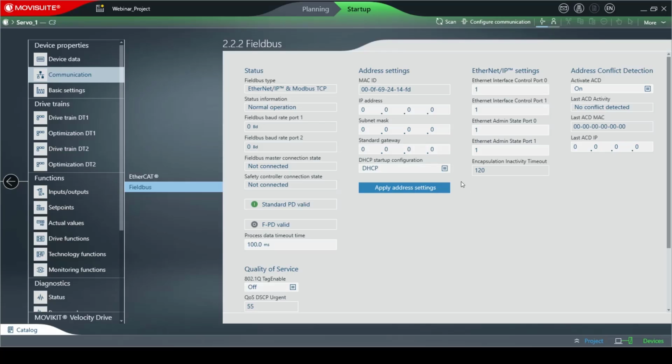First of all, by default, the VFD is using DHCP mode, which causes it to go out to a server and get an address automatically. I'm going to shut this off and tell it to use saved IP parameters instead. I'm now going to type in my information, and I'm going to hit Tab to move from column to column. So I key in 192.168.10.4 for the IP address, and I need to give it an appropriate subnet mask.